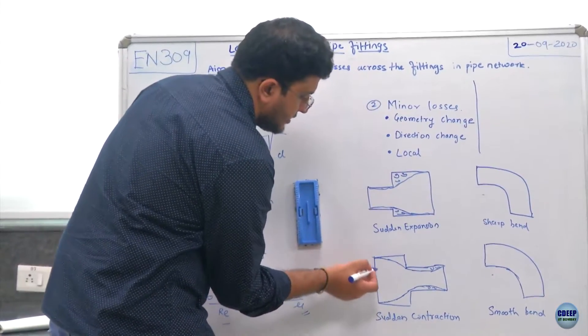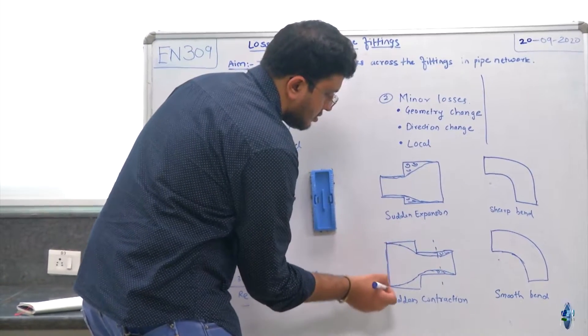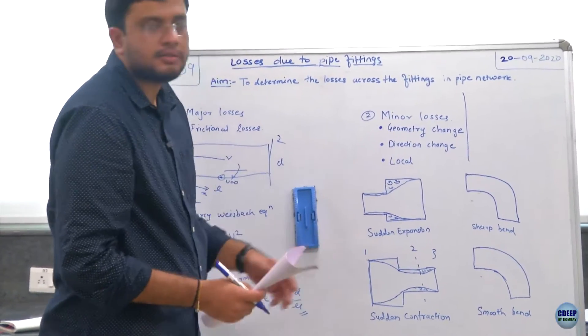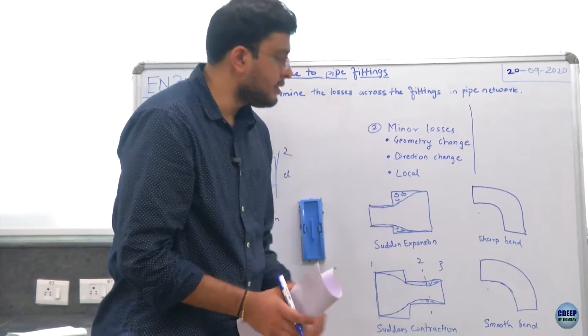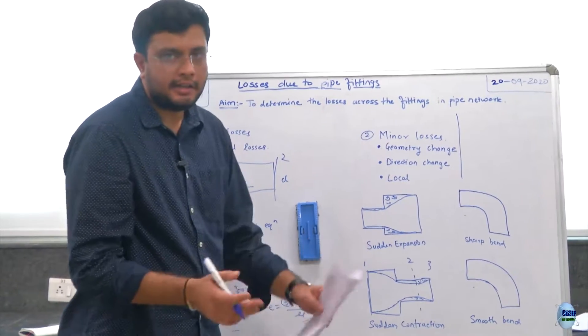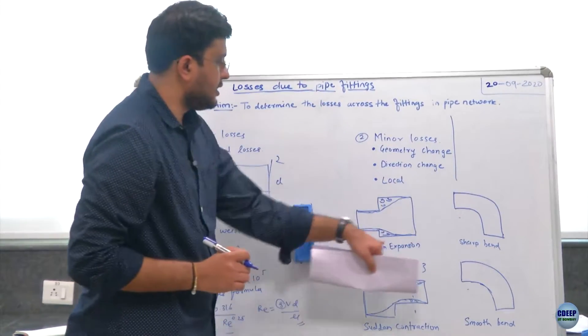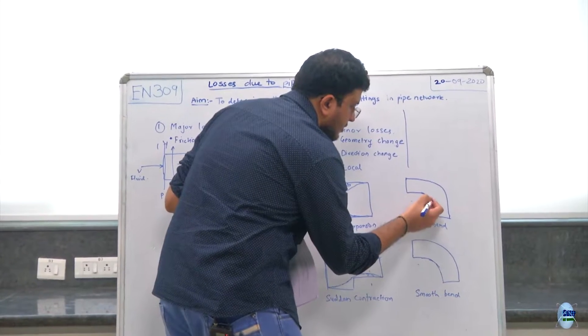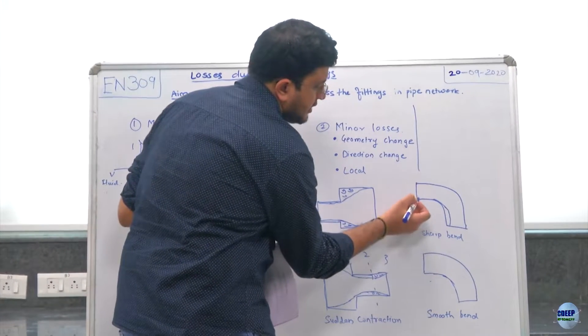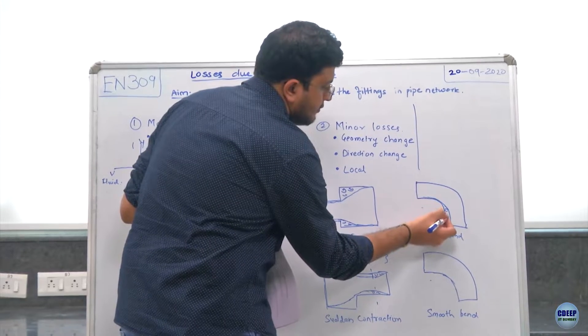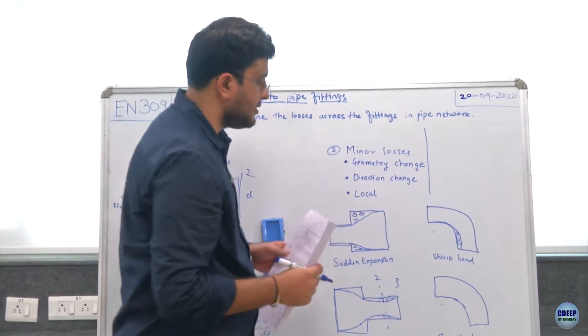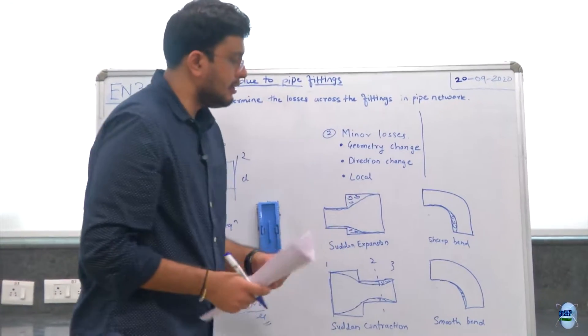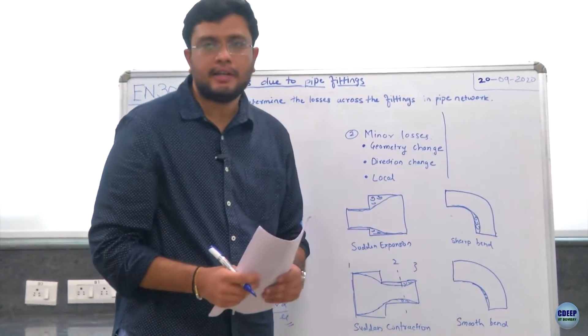In a sudden contraction, we can divide the flow into three sections. From section 1 to 2 the head loss is appreciable, but from section 2 to 3 — which can be considered as a sudden expansion — the head loss is higher. In a sharp bend, due to the sudden change in direction, fluid separation takes place, eddies form in that section, and these eddies are responsible for the head loss. Even in a smooth bend the magnitude of separation is lower, but eddies still form and lead to head loss.